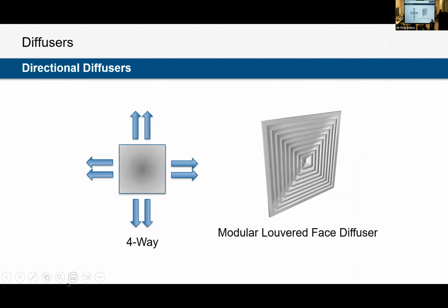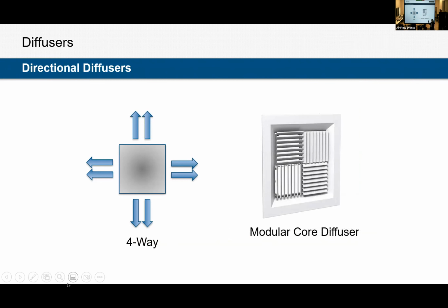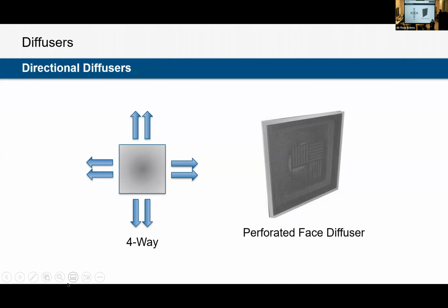Other types of ceiling diffusers, directional diffusers. So this is a modular louvered face in a 4-way pattern. Core diffuser, so it'd be a removable core diffuser, again in a 4-way pattern. I had just mentioned perf diffuser. So you can kind of see behind the perf, there's some directional blades. With the perf diffuser, you get a little bit of direction. And I sort of mentioned the perf is really bad at turn down. Because of that perf screen over the face, as soon as you lower your airflow to a much lower velocity, 70 or 100 CFM, that airflow doesn't go anywhere but straight down. The perf kind of stops any direction to it and dumps it right into the space. If you ever go into a Chick-fil-A, almost every Chick-fil-A has perf diffusers, and they're the cheapest but probably the worst performing diffuser. We'll just say that.